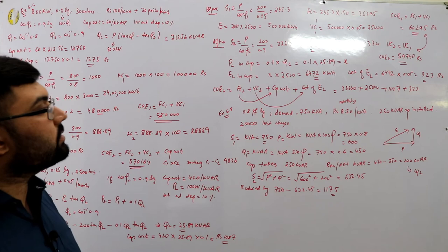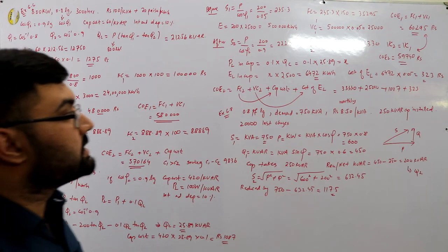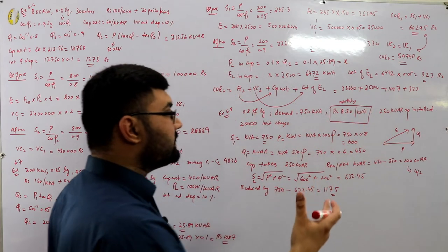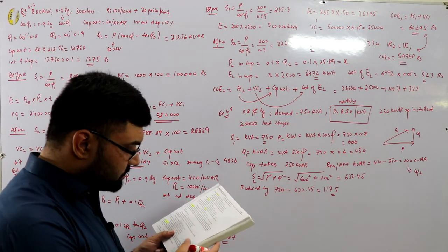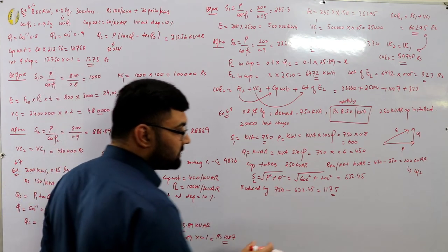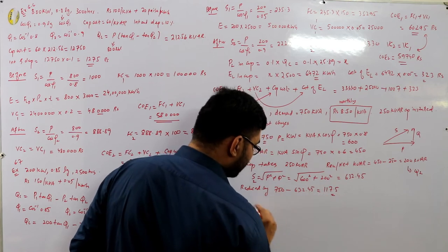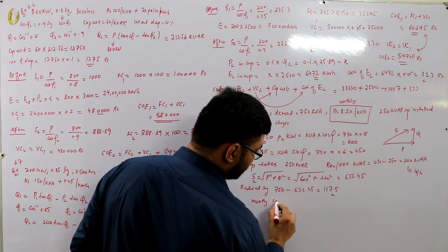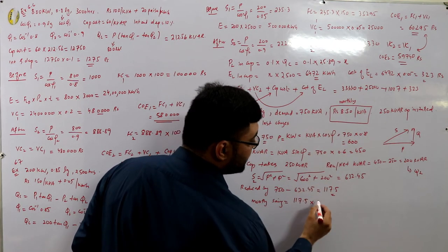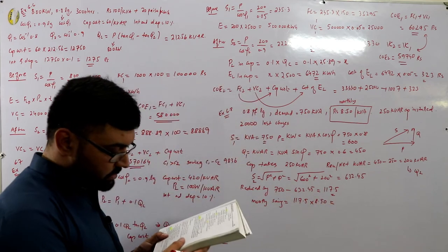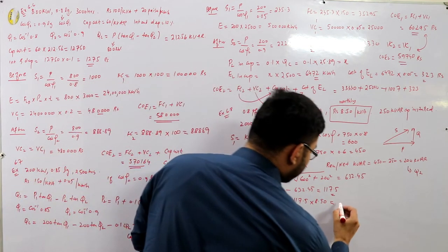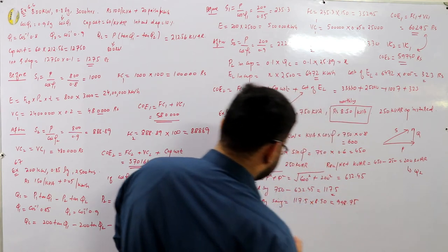Now you are only given the charges on the basis of kVA. So you have to calculate the charges for kVA, which means you have monthly saving. You have reduced it by this much amount, so you have saved this much. So monthly saving would be this amount of kVA multiplied by the cost per kVA, which is 8.50. So this comes out to be 998.75. This is the monthly saving.